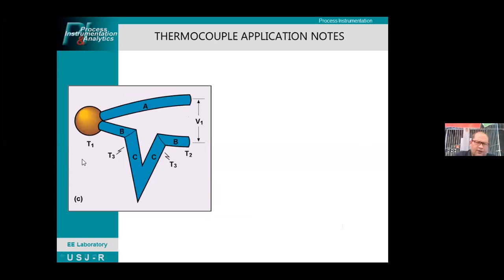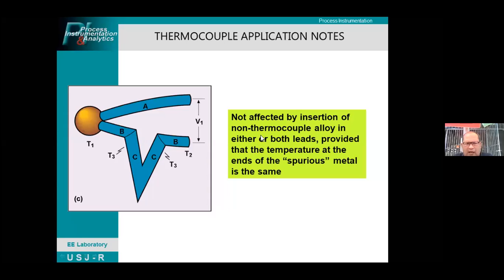Another modification of this thermocouple application: for metals A and B, you put a metal C in between, where metal C at this part is being heated, but the joint, the soldering or welding, is at the terminal between metals A and B. Still, the output is not affected by insertion of a non-thermocouple alloy, such as this metal C, in either or both leads, provided that the temperature at the ends of the spurious metal is the same. So it does not affect the output of metals A and B.